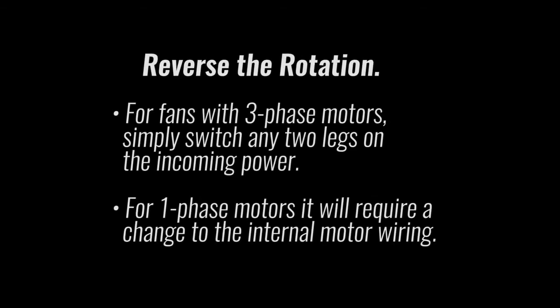The fix for this is simple. Reverse the rotation. For fans with three-phase motors, simply switch any two legs on the incoming power. For single-phase motors, it will require a change to the internal motor wiring.